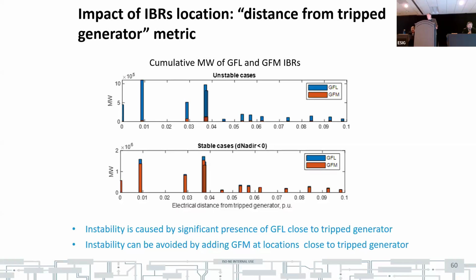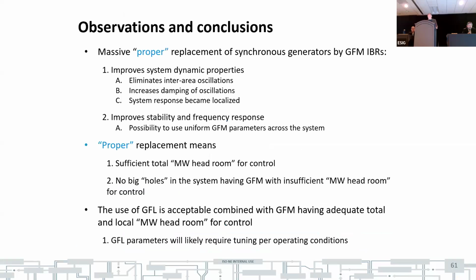And that graph shows the same statistics, but with a different metric, which is the proximity or distance of the inverter from the generator which is tripped during contingency. The logic is absolutely the same. So if you have a lot of grid following inverters around, that results in instability problems, and the opposite. If you have a proper combination of grid following and grid forming, you have good results.